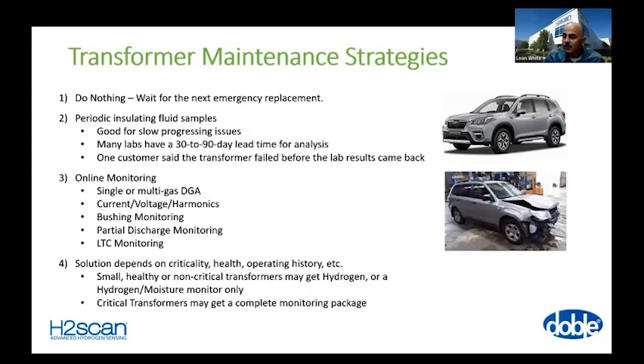This customer had some high industrial lighting loads that were generating lots of harmonics and failing like 2 MVA transformers after a couple of years. They said in some cases they've seen where last year's sample looked fine. They took an oil sample, and before the sample came back this year, the transformer had already failed. That's typically not going to occur, but it's a concern. They also indicated that when they tried to rush a sample at one of their labs, it's a transformer service company, and they used several labs, it still took like 30 days to get a rush sample back.